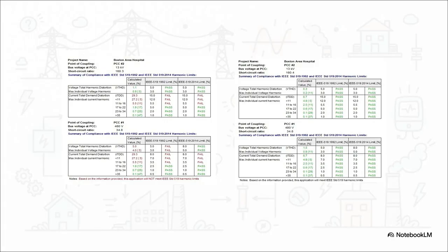This is the proof in the pudding: a real report from a hospital. On the left, it's just a sea of red fail marks, they were completely out of compliance, way over the limits. But look at the right: after engineers went in and installed the right harmonic filters, bam, all green, all pass. It's such a perfect example that yes, this is a huge problem, but it's a solvable one.